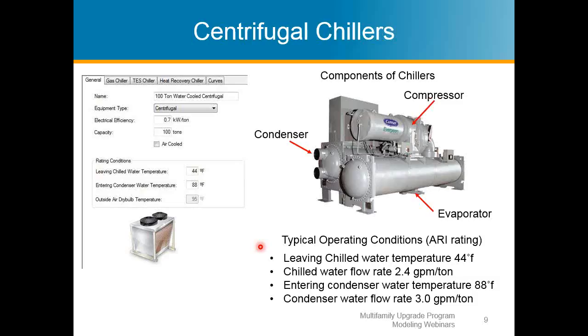Inside these barrels of the chiller, there's a bunch of different tubes, and they're very small. Could be hundreds of them, depending on the size of your system. That's where the water is flowing through, and it's getting either cooled down or being taken to your condenser to the outside unit. So the evaporator has a bunch of pipes inside with the water running along them, and then it leaves to go to your indoor unit.